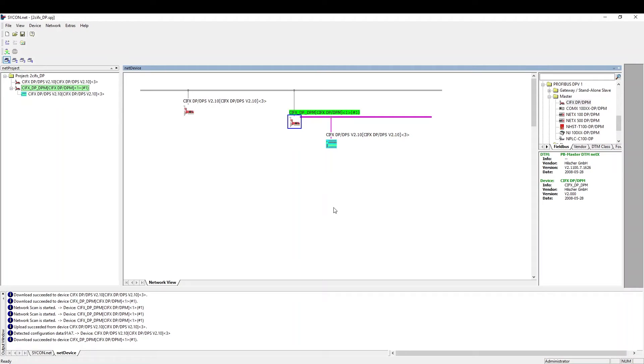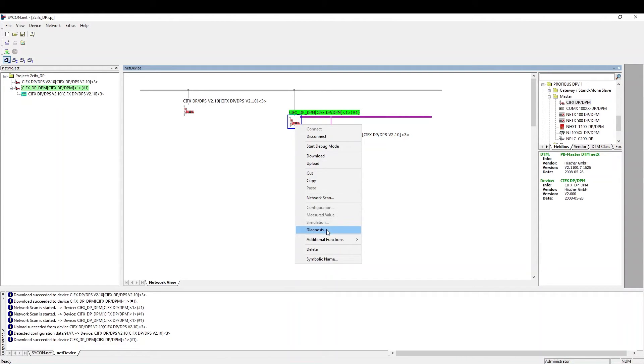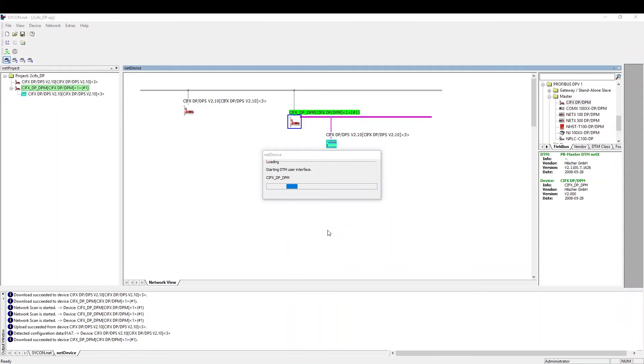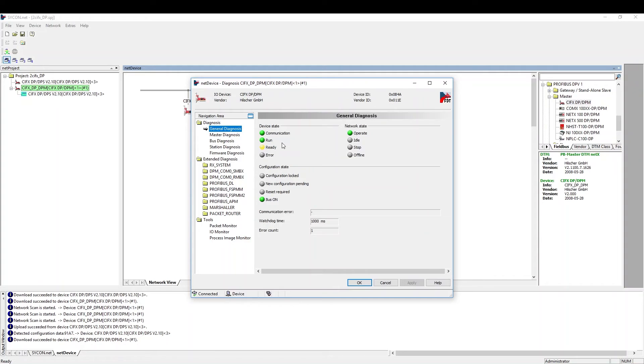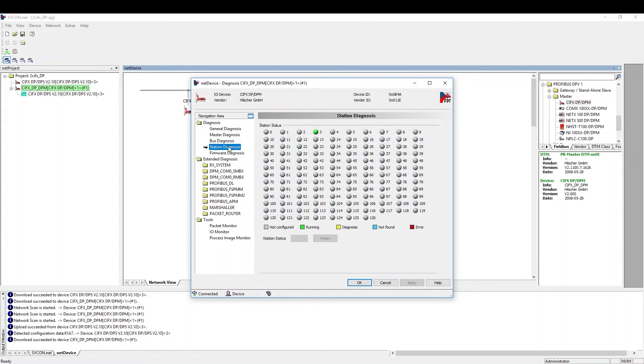Next, we check the diagnosis. Everything is working fine. If there were to be an error, you could first check the station diagnosis to determine the specific slave. We can then take a look at the diagnosis of the particular slave to further investigate the issue.